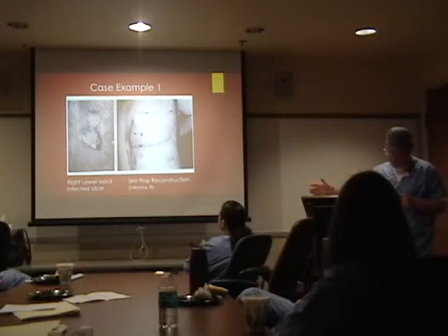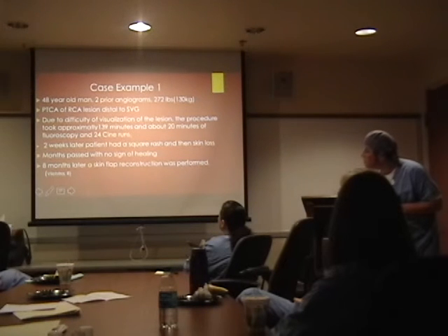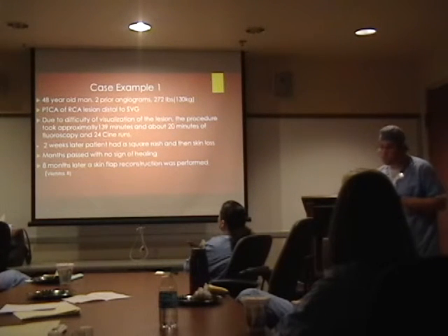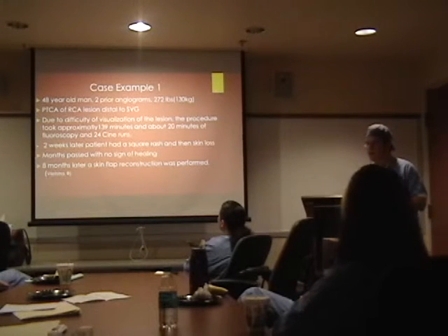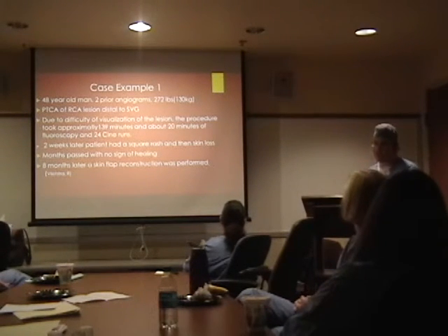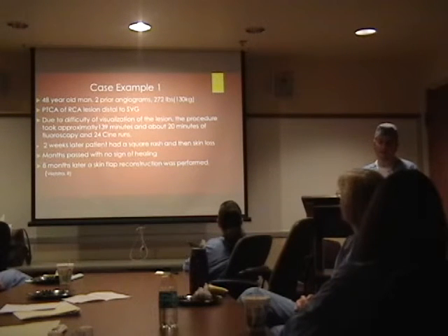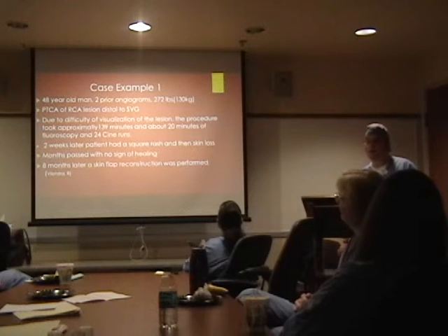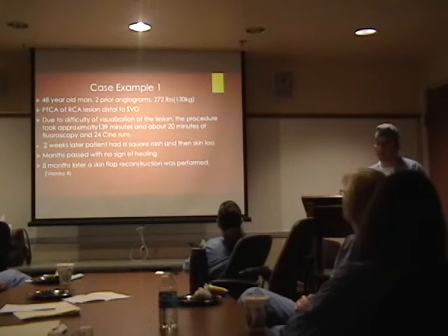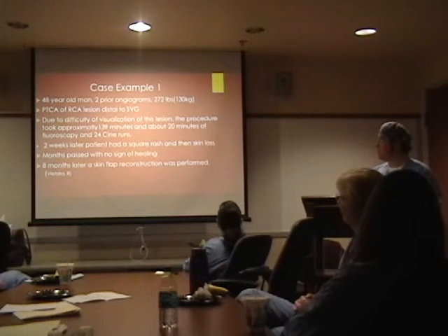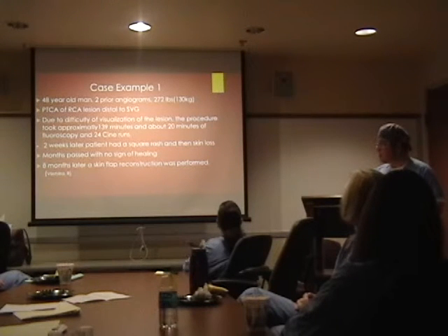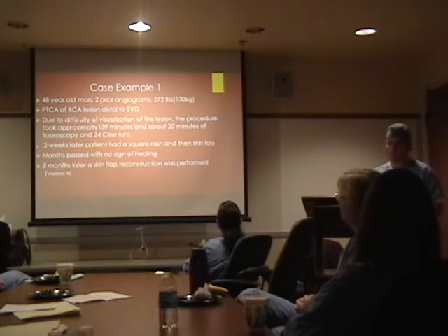if they said, okay, well, you did have excessive fluoro. Let me back up here. So again, he had 20 minutes of fluoroscopy. Only 20 minutes. I was watching a case a couple weeks ago, at 13 minutes, it hit 2 grays on the monitor. But we don't give them a letter till 40 minutes now. So should we be giving the letter at 40 minutes, or should we be giving the letter when it hits 2 grays? And Dr. Fishbein has been reading and doing some extensive research about radiation safety. So I think he does a good job as far as being concerned and being aware of this.